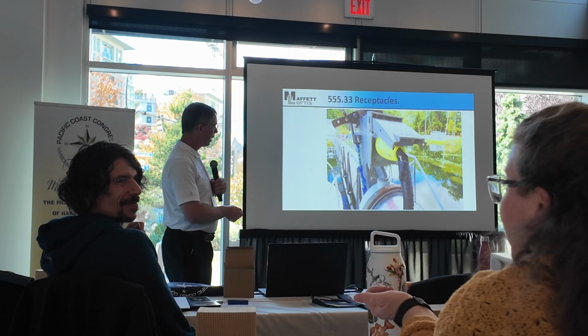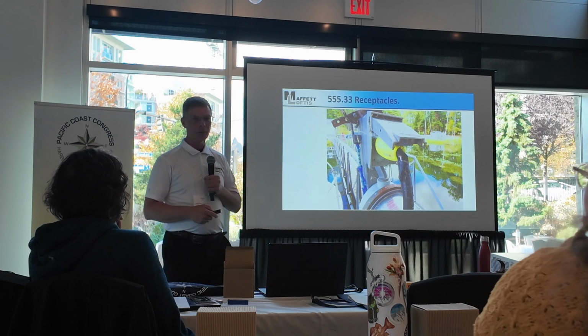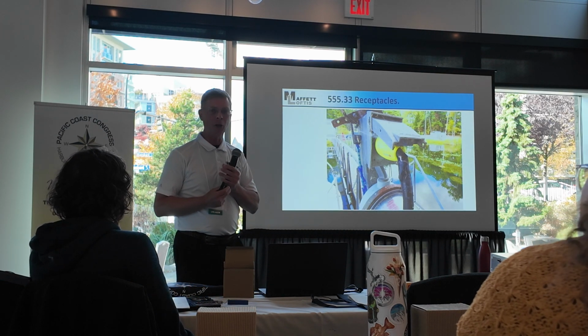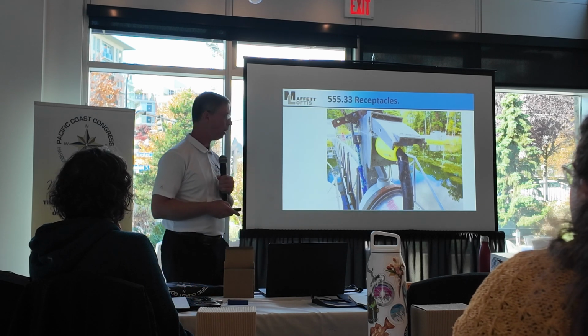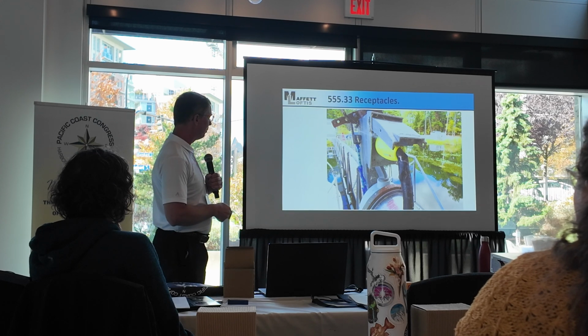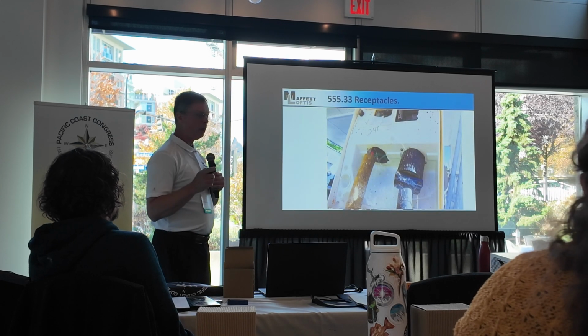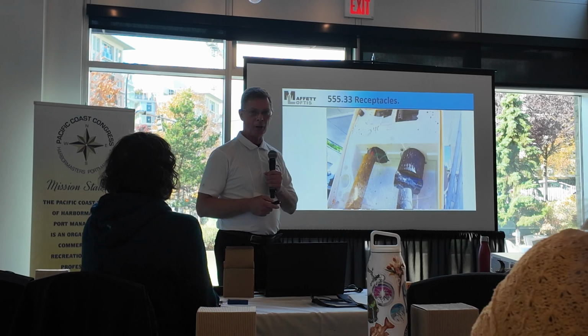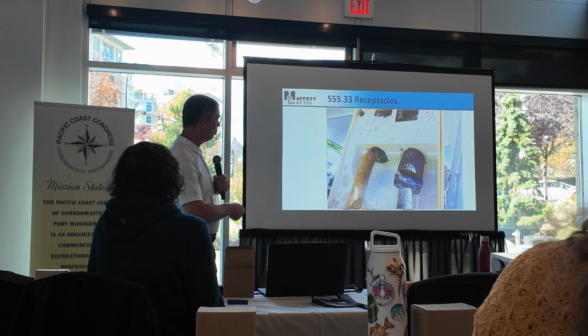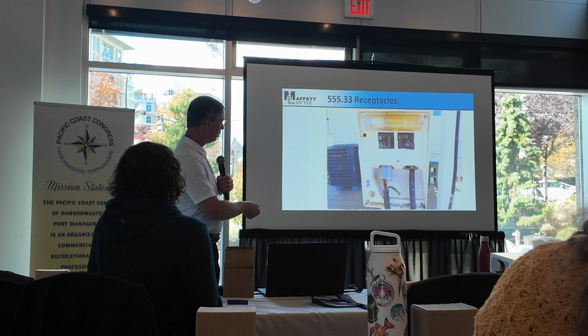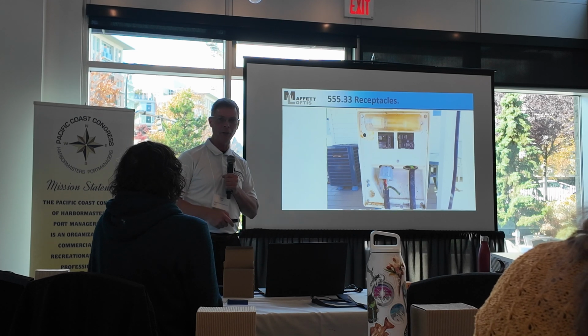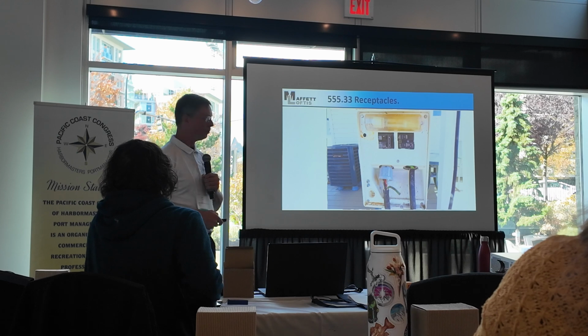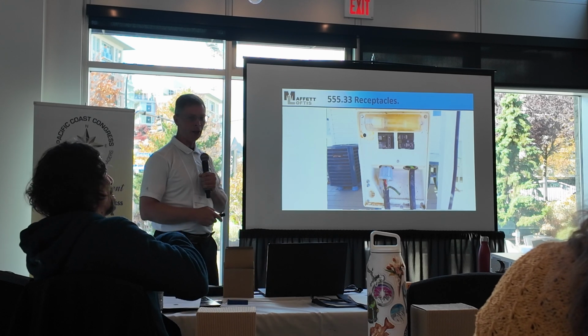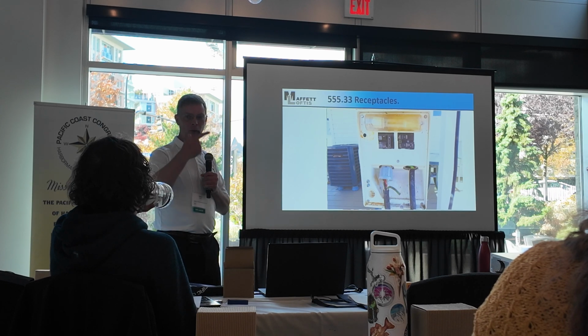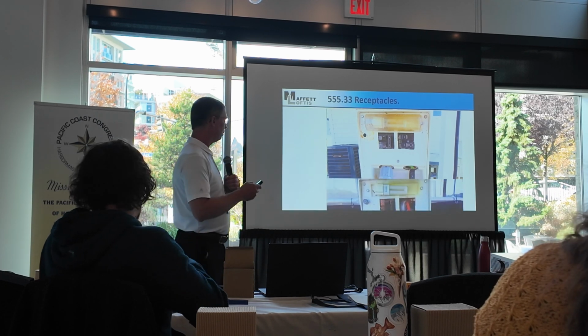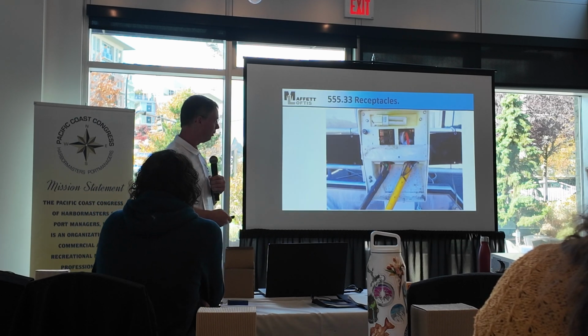Okay, look at the type of cables that people are using, homemade cables. I'm not saying homemade cables are going to just disappear, but they need to be safe, as you're walking your dog. None of this is very good, and the cable's really bad off. That's a nice fiber one. Do open up the lids of your shore power pedestals every now and then, because the marina owner did not even know that they had done this. And look, do you think that green wire back there just hanging out is a good thing? Well, it was causing an issue on his boat. Yeah, it probably was. Or they just hardwired right into the breaker here, didn't have a disconnect. And they never raise up the lid to look. Two minutes, Gary. Ten minutes, right? And this happens a lot more than you think. There's another one, both of them.